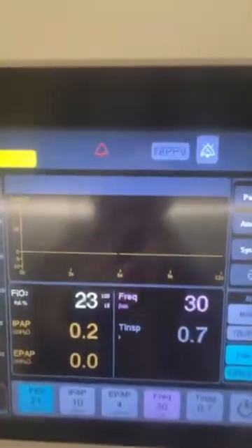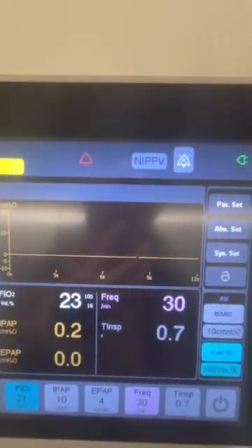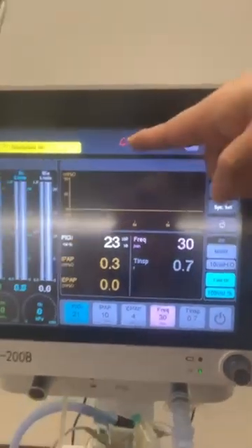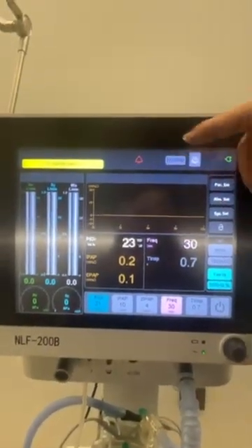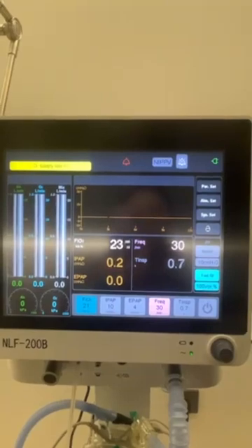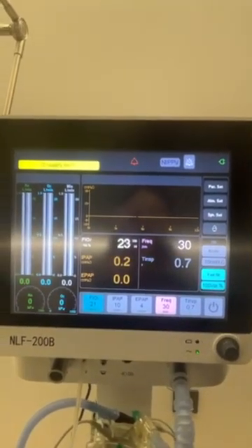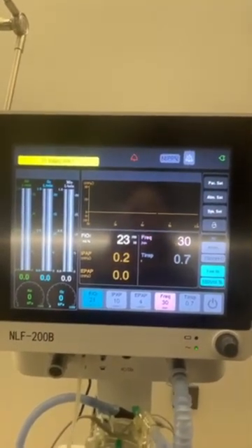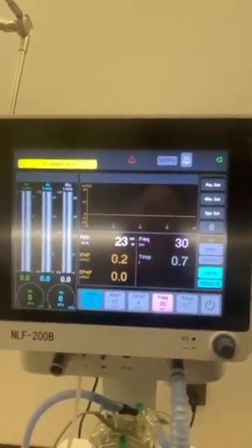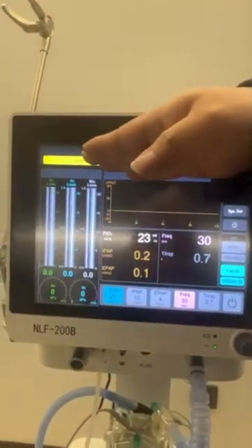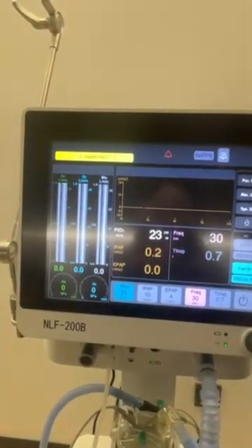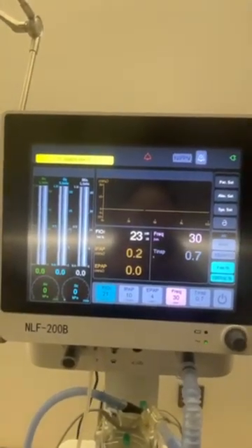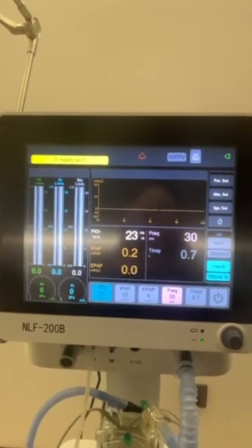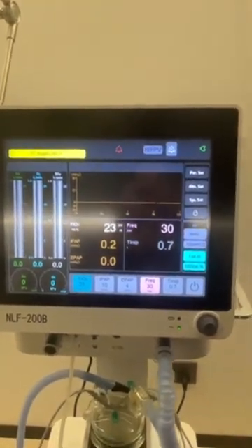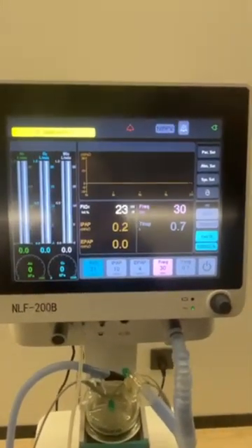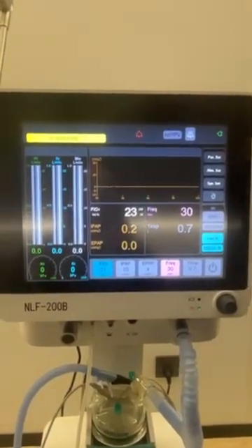This actually is a mute button. Once we mute the machine, here it will have a symbol with the time counting 2 minutes. That means for the next 2 minutes, the machine will be totally muted and silent. It is only used for some time, if the doctors think the alarm's information does not influence the patient's use, and we don't want the machine to be very loud and influence the operation. Then we can just press the mute button.